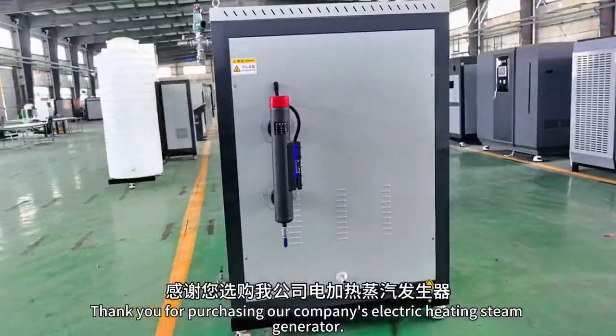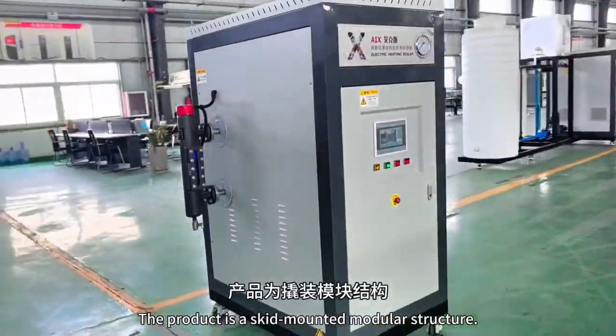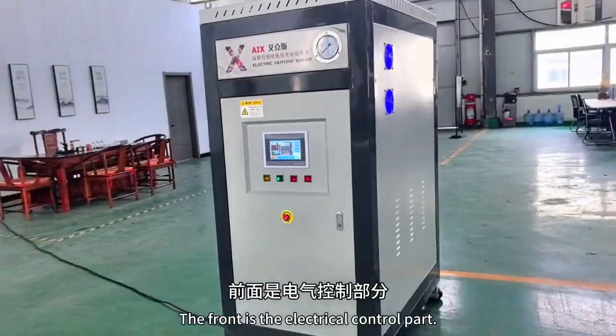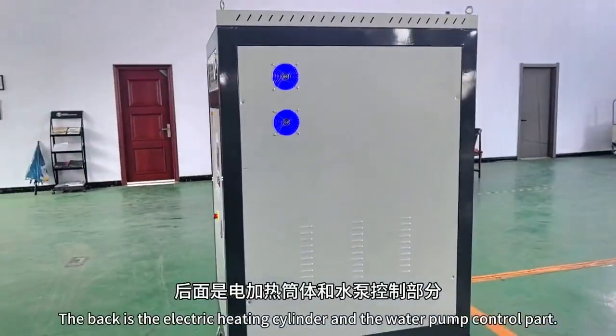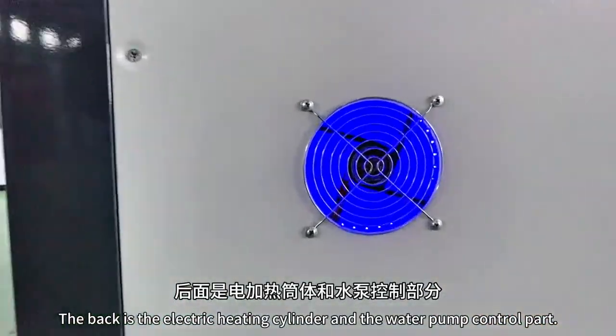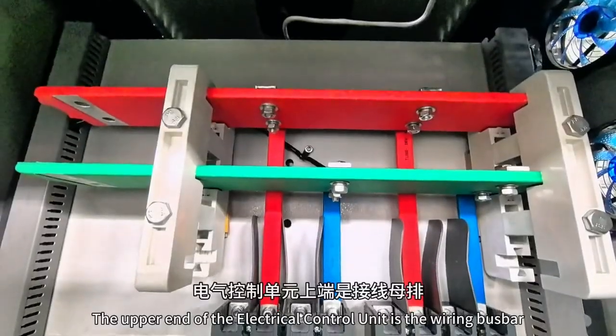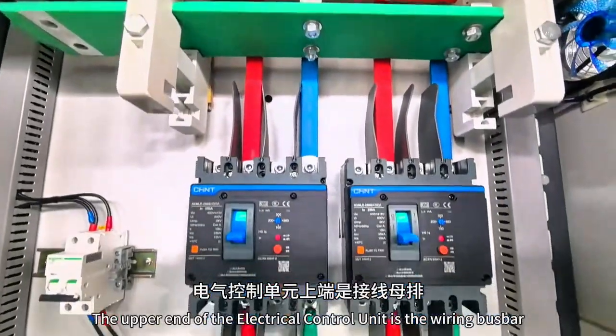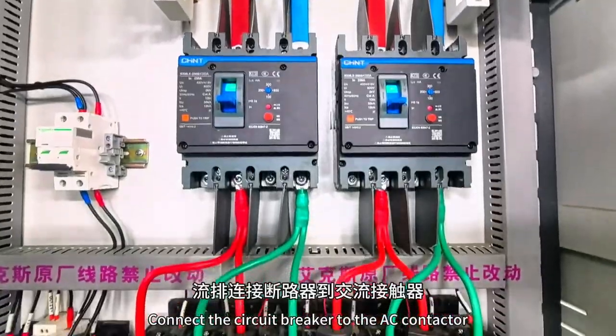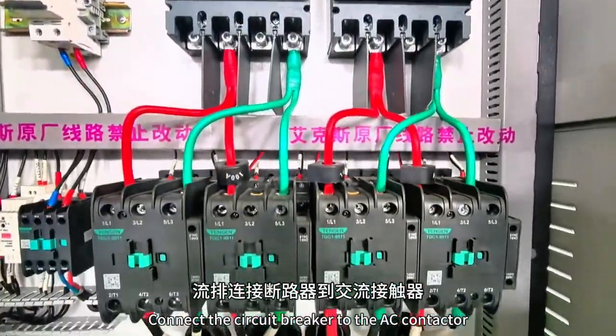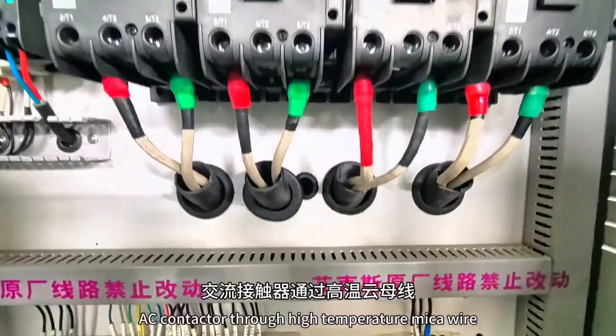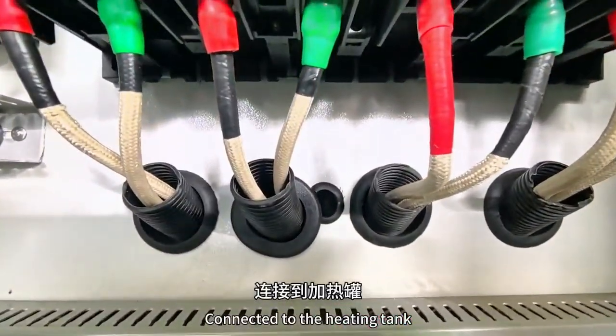The product is a modular structure with a prime-mounted structure, with the front part being the electrical control part, and the back part being the electric heating cylinder and water pump control part. The electrical control unit has a wiring busbar at the upper end, which connects the circuit breaker to the AC contactor. The AC contactor is connected to the heating tube through high-temperature mica wire.